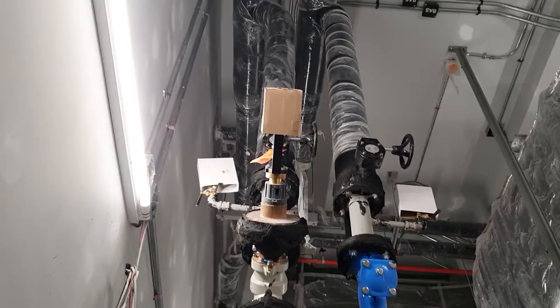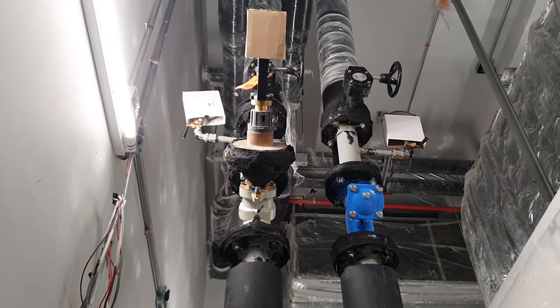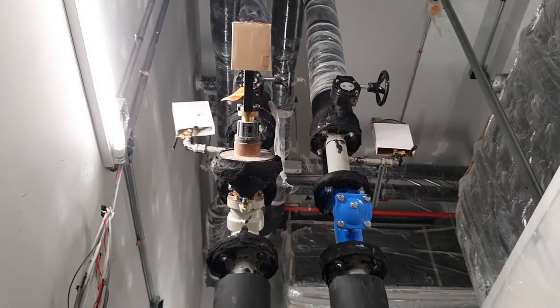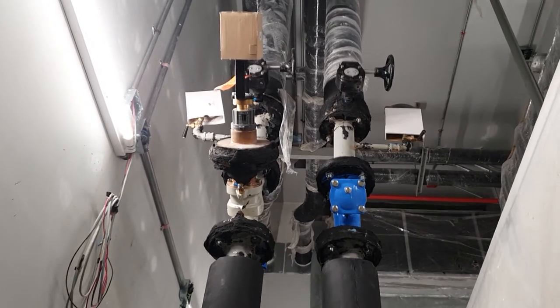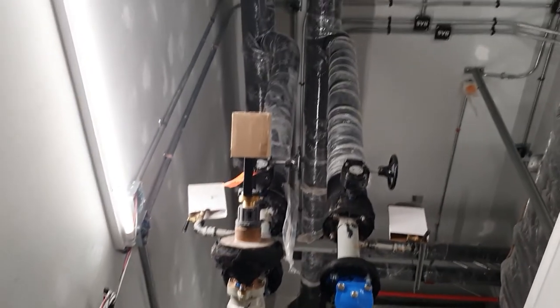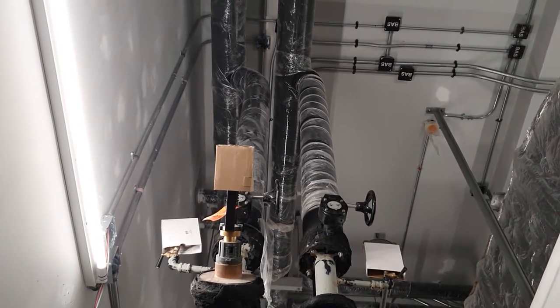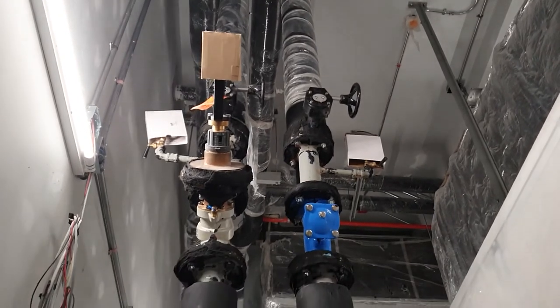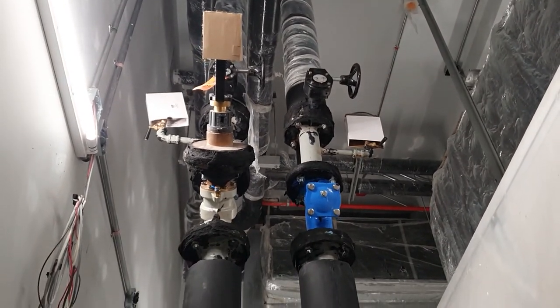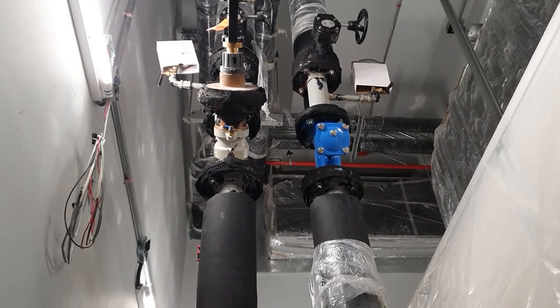For this AAU, we connect the PVC piping in the loop for flushing. After the flushing is finished, we will connect it to the AAU system. We will then start the operation of the chiller with the AAU and FCU.